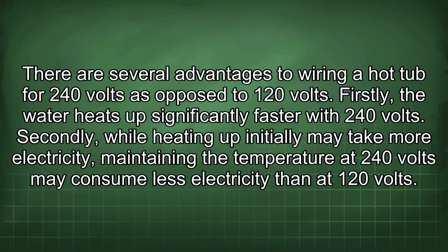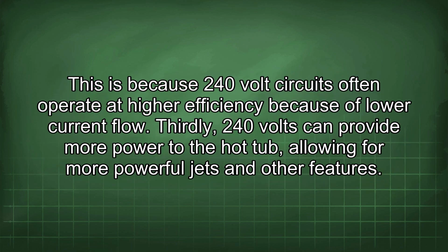There are several advantages to wiring a hot tub for 240 volts as opposed to 120 volts. Firstly, the water heats up significantly faster with 240 volts. Secondly, while heating up initially may take more electricity, maintaining the temperature at 240 volts may consume less electricity than at 120 volts. This is because 240 volt circuits often operate at higher efficiency because of low current flow.